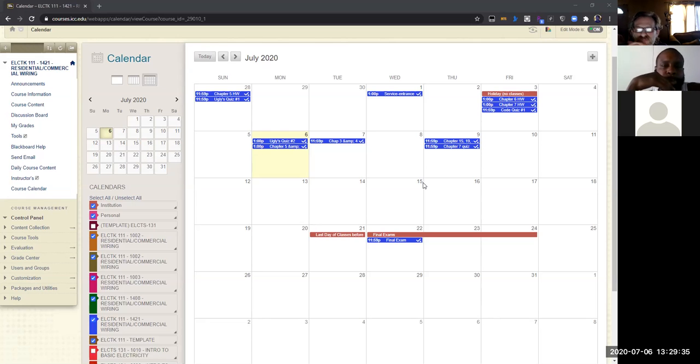Like I say, go through and do these upcoming homeworks, chapters 15, 19, and 23. It's all about appliances and hookups. So most of our calculations will be figuring out what our current ratings are supposed to be for the disconnects, for the circuit breakers, that kind of thing. Remember the heating element styles have to have 125% duty cycle to them, versus the dryer styles where it's just standard. But that'll be about the trickiest we get with the calculations for any of that stuff.